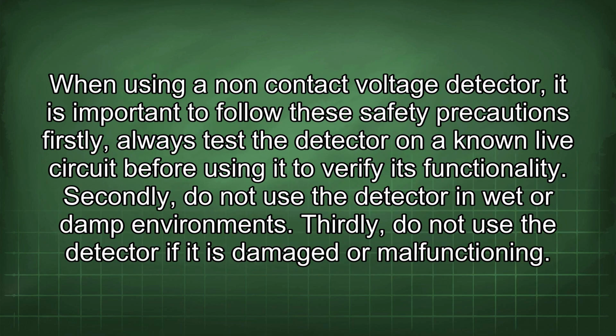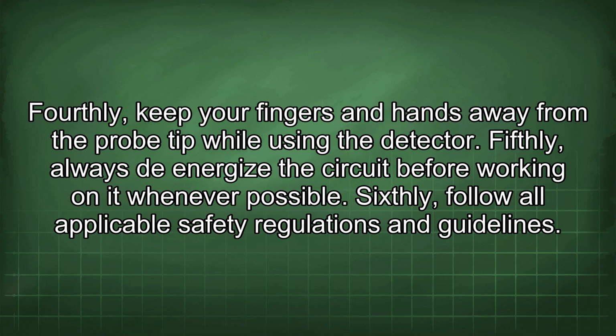When using a non-contact voltage detector, it is important to follow these safety precautions. Firstly, always test the detector on a known live circuit before using it to verify its functionality. Secondly, do not use the detector in wet or damp environments. Thirdly, do not use the detector if it is damaged or malfunctioning. Fourthly, keep your fingers and hands away from the probe tip while using the detector. Fifthly, always de-energize the circuit before working on it whenever possible. Sixthly, follow all applicable safety regulations and guidelines.